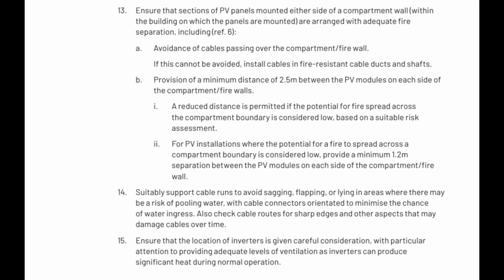Suitably support cable runs to avoid sagging, flapping, or lying in areas where water might pool. Cable connectors should be oriented to minimize the chance of water ingress. Regularly check cable routes for sharp edges or other potential damage that could occur over time. This is especially important in our climate here in Britain, where we can experience quite a bit of rain. Ensure that the location of inverters is given careful consideration, with particular attention to providing adequate levels of ventilation. Inverters generate significant heat during normal operation, and proper ventilation is essential for their efficiency and longevity.